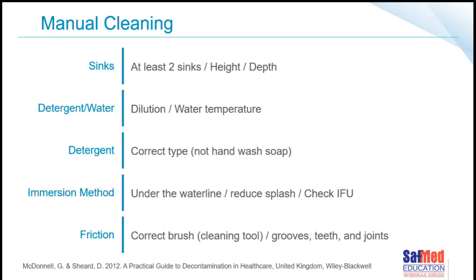Then, what method of cleaning is it? Am I going to immerse it? Can I immerse it? Is the device able to be immersed? If I am immersing it, that's great, because I want to wash under the waterline to reduce splashing as well as aerosolization of microorganisms. Check the instructions for use.